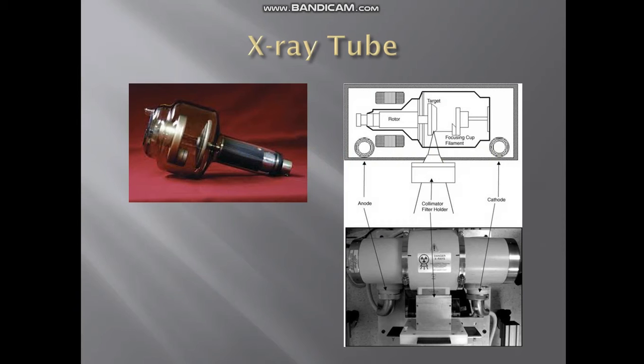The X-ray tube is responsible for producing electrons from the filament through the process of thermionic emission. These electrons are directed and bombarded towards the target of the anode, causing the kinetic energy possessed by the electrons to be converted into heat and electromagnetic energy.